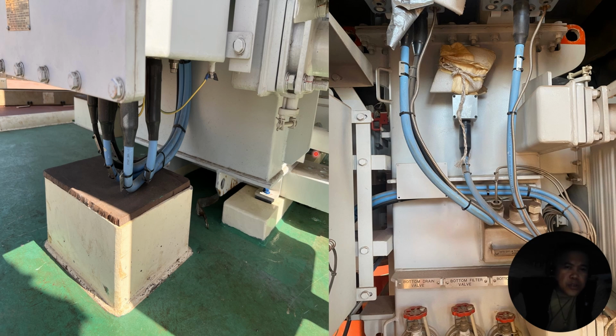Now the issue here when installing your equipment, as you can see in this area - this is the penetration, this is the cutout, this is the plank. Meaning you have some cables to be installed in this area, so you'll remove this and the cable will enter in this portion, with glanding and termination later on. You can see the bending of this cable - it's totally not appropriate, and it's hitting the metal, the frame, the cutout.